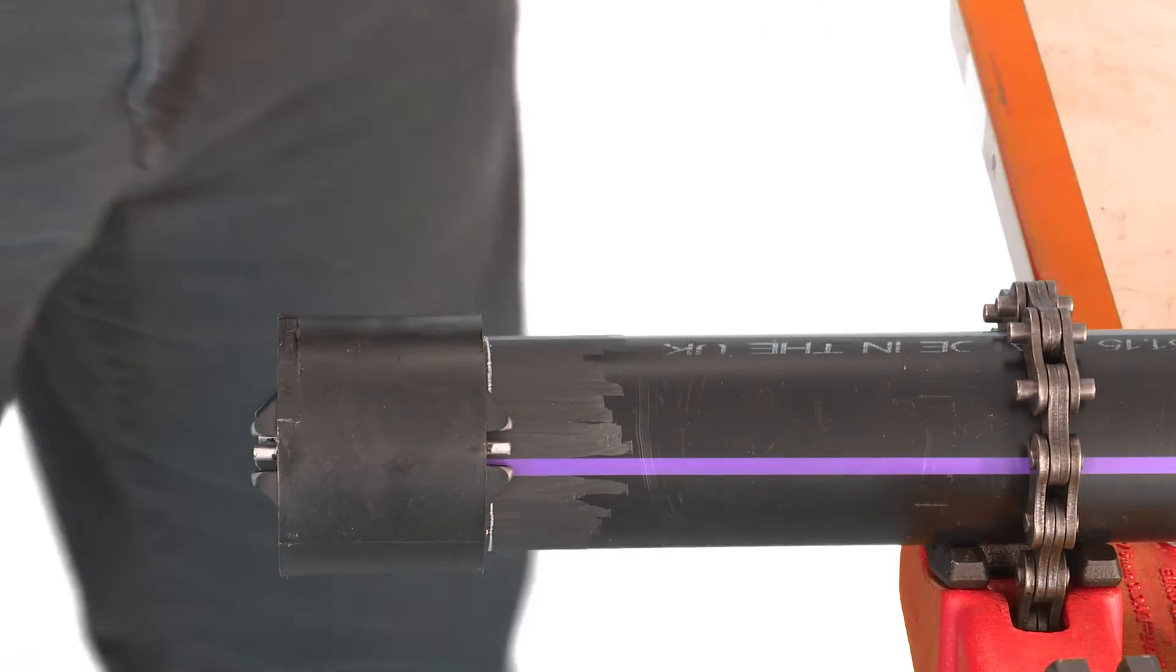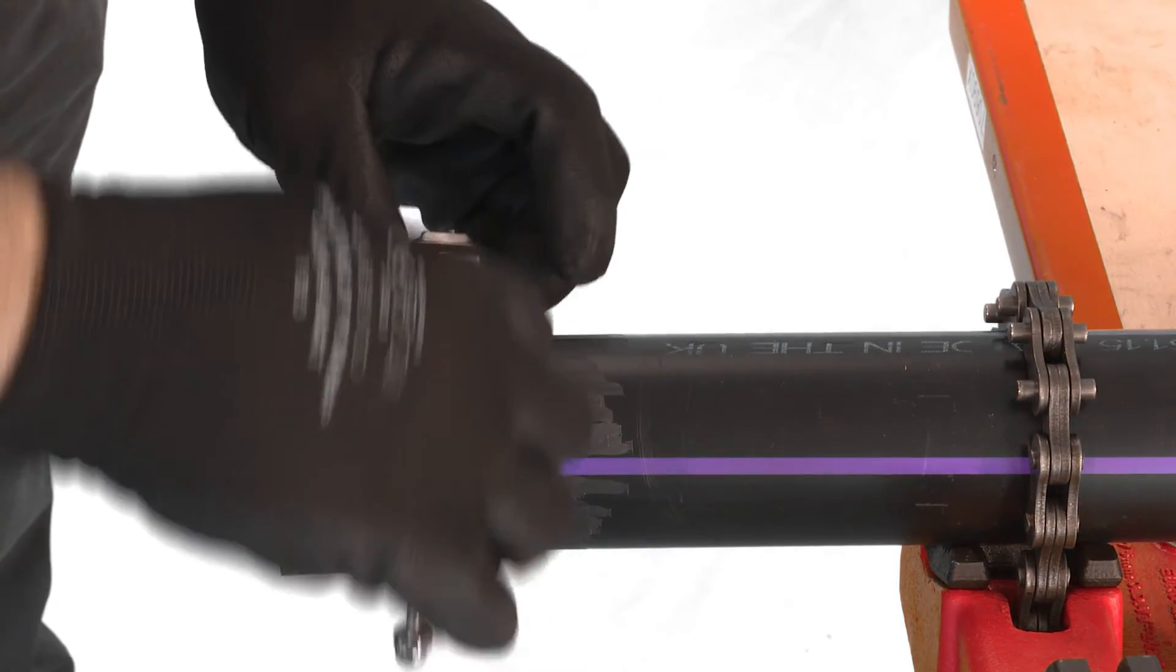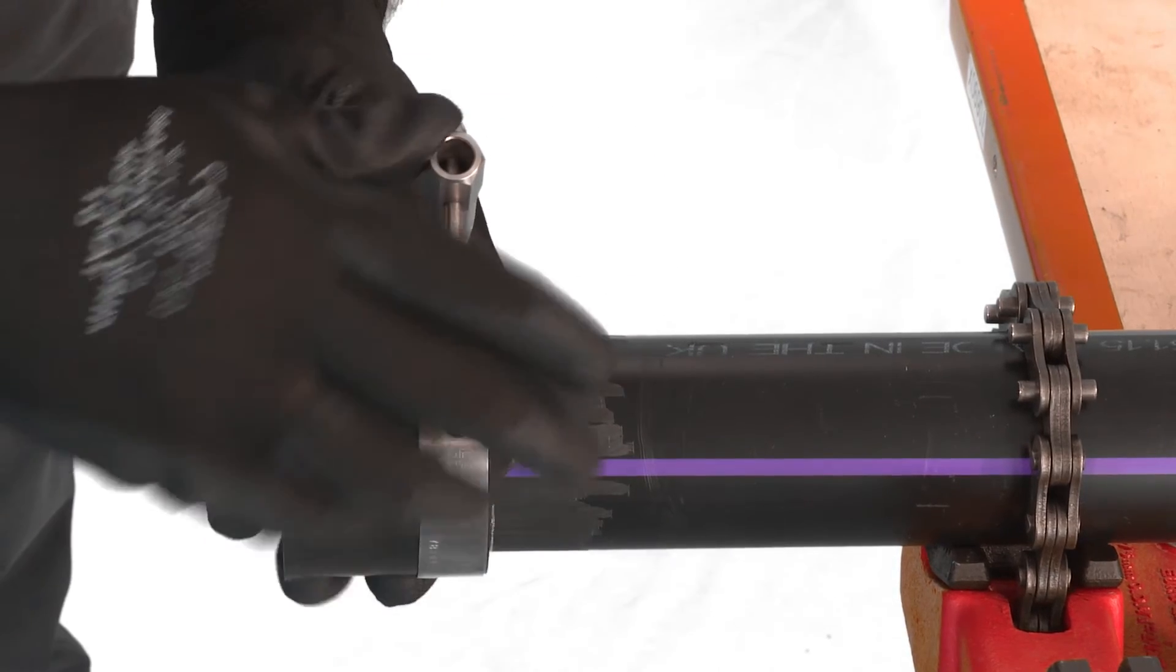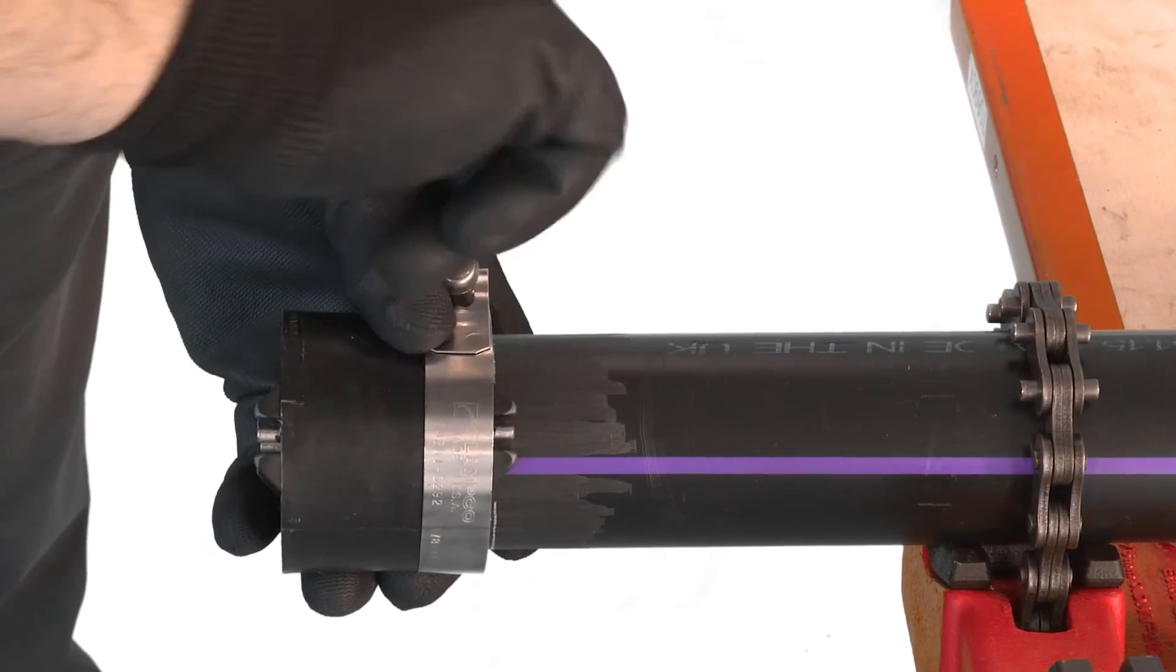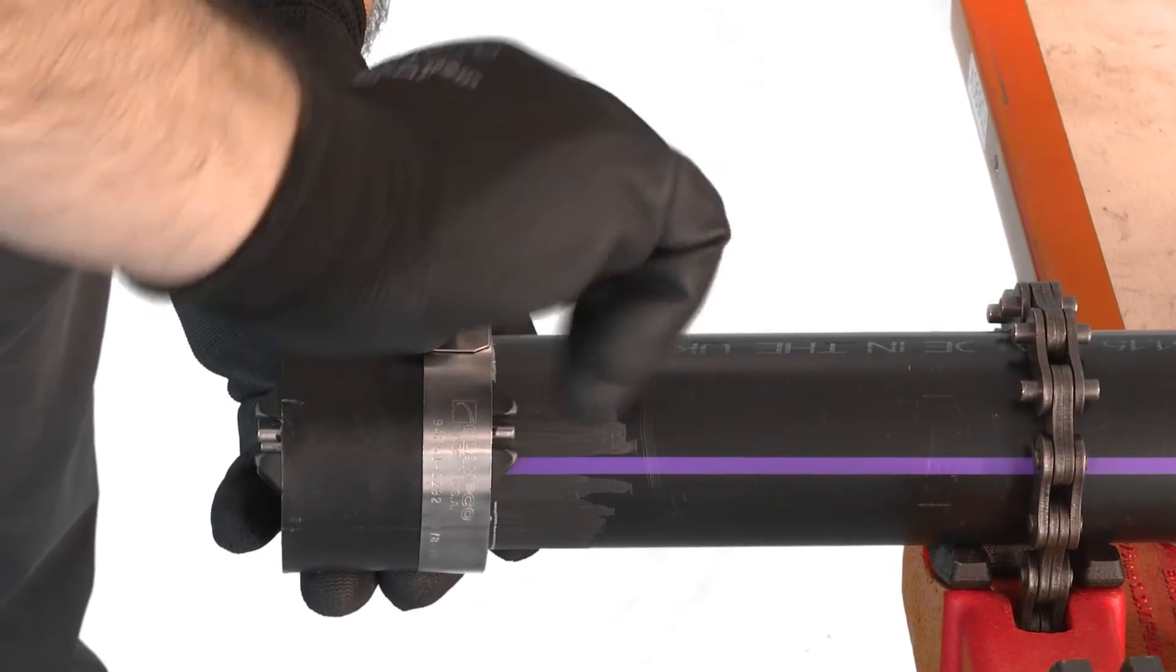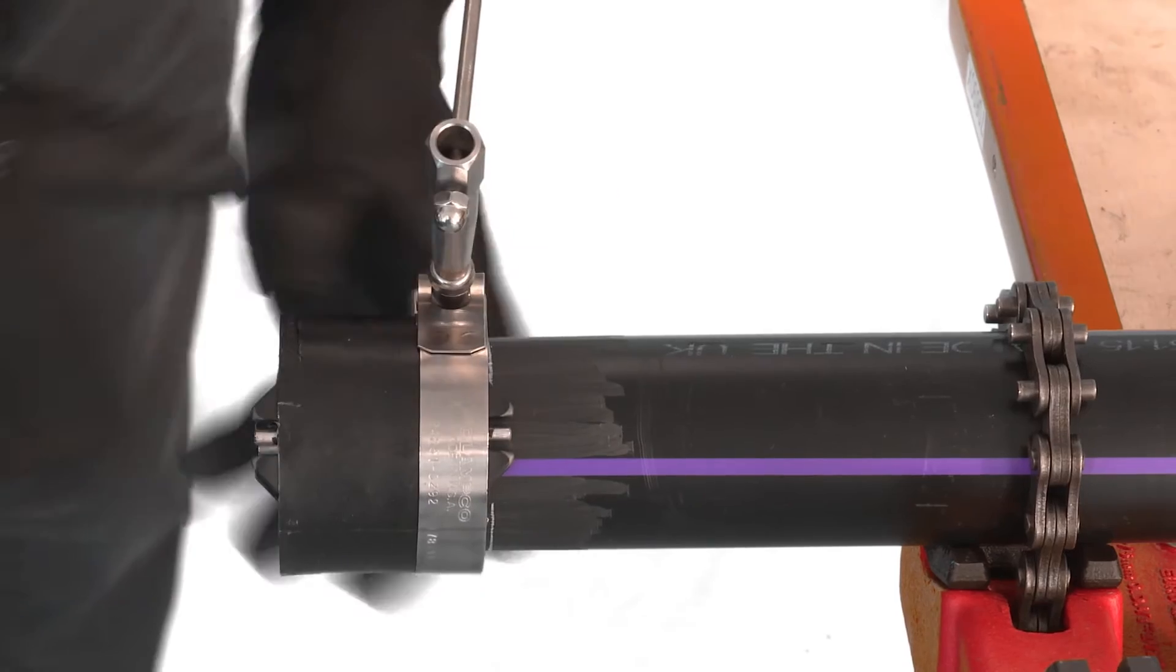Loosely fit the appropriate sized clamp over the hub of the socket and position flush with the end of the socket. Tighten the clamp around the hub. It's important that the clamp is tightened sufficiently to stop pipe rotation in the socket. Do not over-tighten.